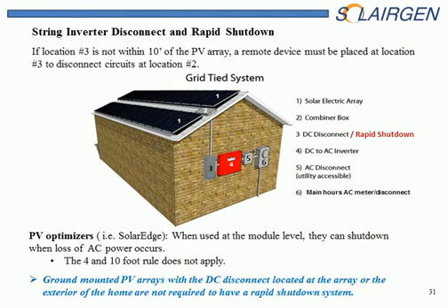So if you see a DC and an AC disconnect and an inverter in between them, you know that it's a string inverter. Could be that this string inverter is on the inside of the structure, and it could be that the DC disconnect is inside the structure too. But if you see on that number 5 the AC over there and it says a rapid shutdown system in place, then you're safe. The rapid shutdown requires that within 10 feet on the outside there has to be a disconnect, so you know that there's no conduit running in other parts of the structure hiding this high voltage DC.